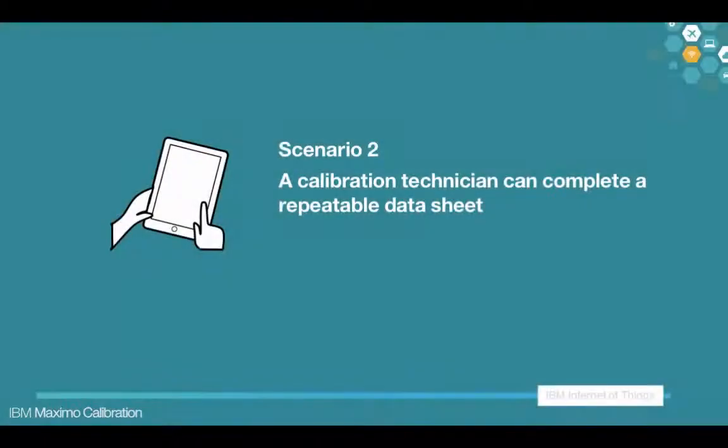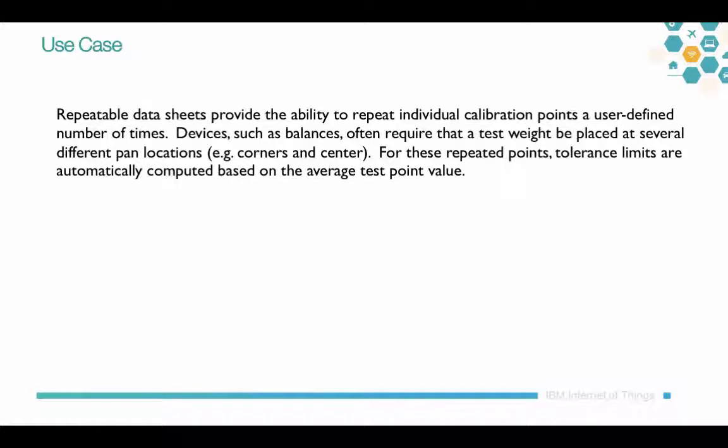The next scenario we're going to take a look at is the completion of a repeatables datasheet. Repeatable datasheets provide the ability to repeat individual calibration points a user-defined number of times. These are for devices such as balances that often require a test weight to be placed at several different pan locations, around the corners and the center. For these repeated points, tolerance limits are computed based on the average test point value.